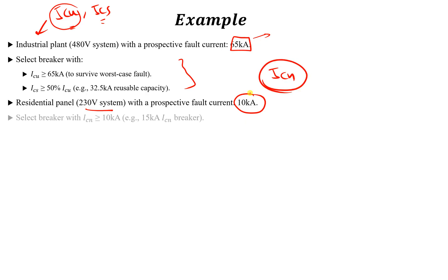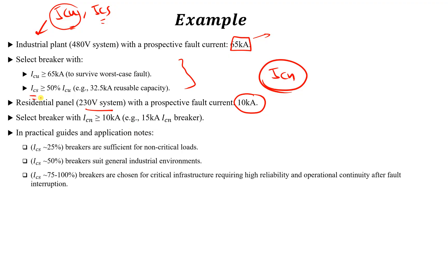In practical guides and application notes, the typical ICS selection is: 25% of ICU for non-critical loads where a breaker failure is acceptable, 50% for standard industrial environments, and 75% to 100% for critical infrastructure requiring high reliability. These are the three important definitions — ICS, ICU, and ICN — and their applications. Hope you understand them well.